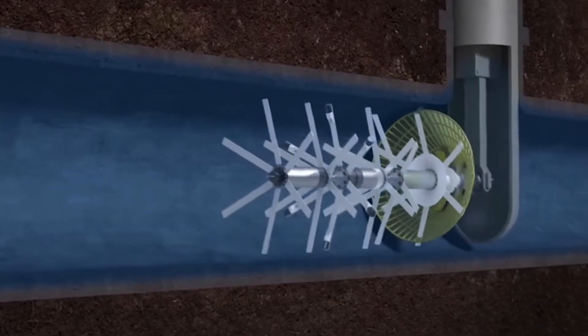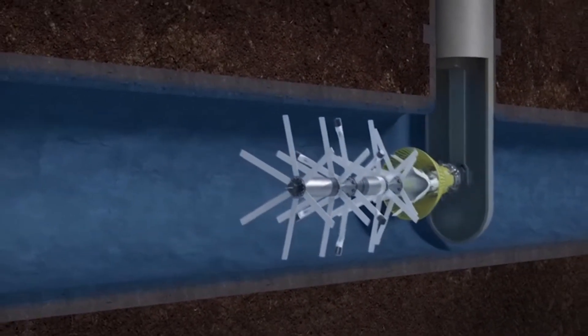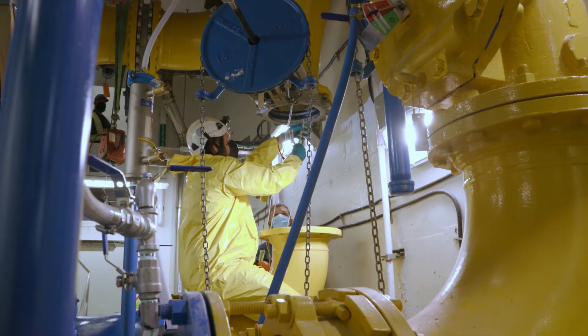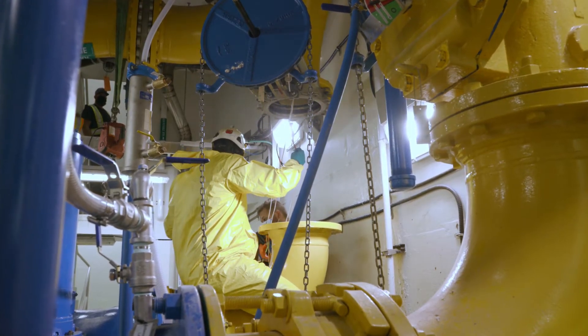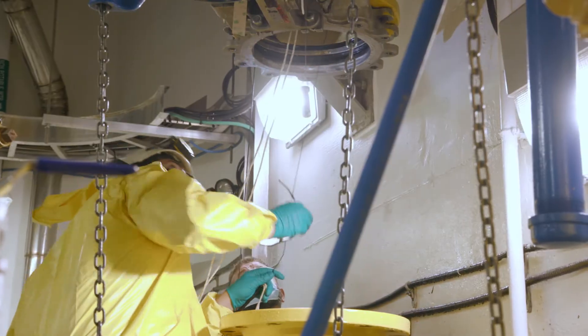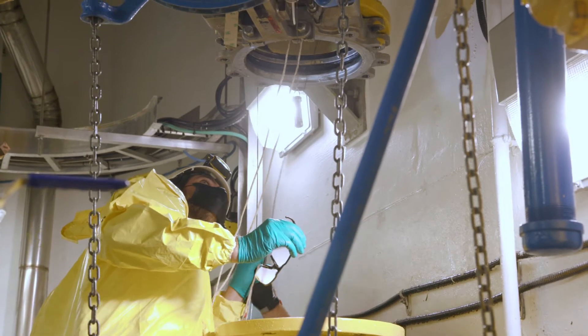This operation requires coordination between several groups. We have an operations team here to operate the pump station and lock out the pump. We have Pure Technologies here who is inserting the Pipe Diver tool and collecting the data for the force main inspection, and we have Absolute here to do the removal and installation of the check valve.